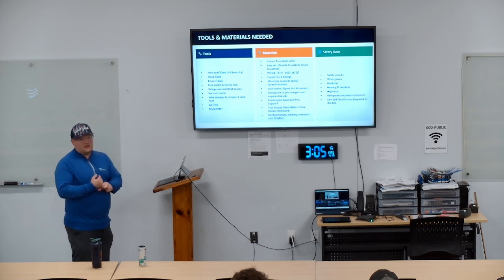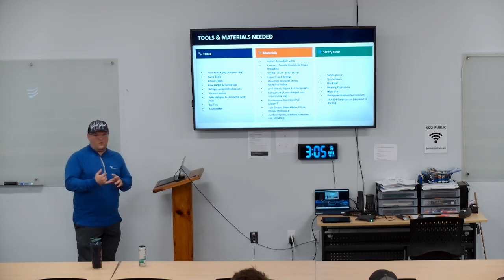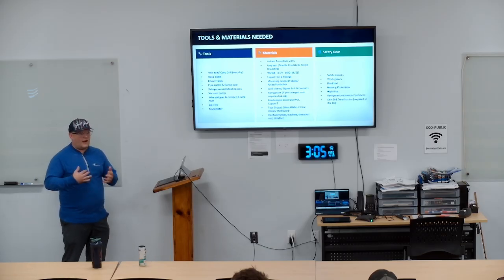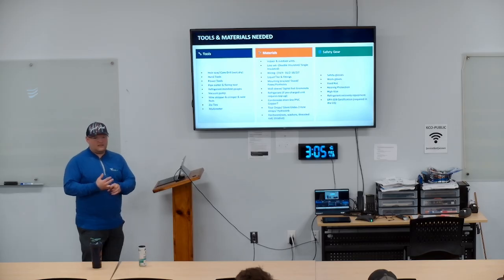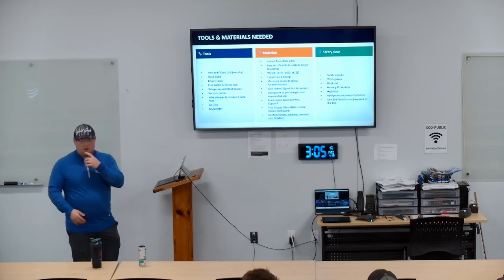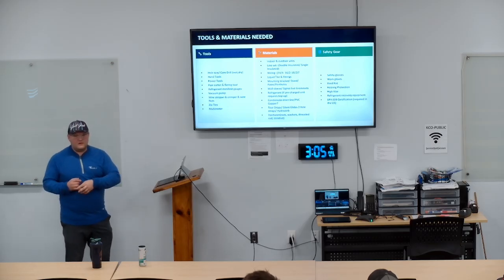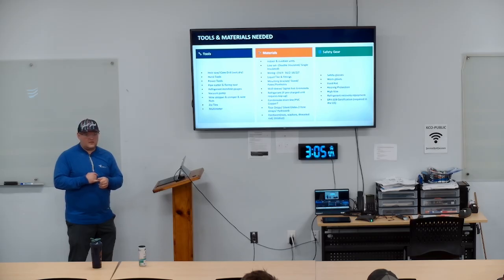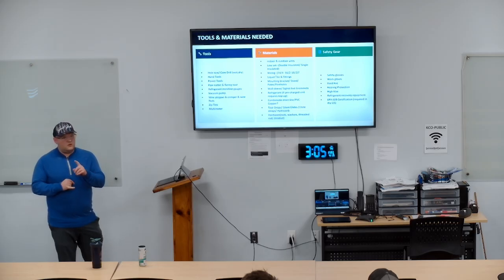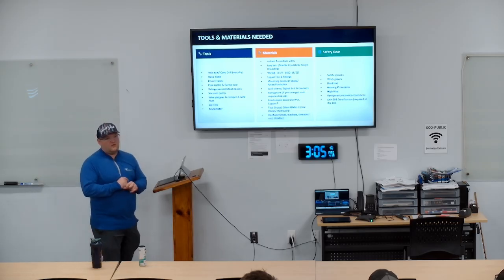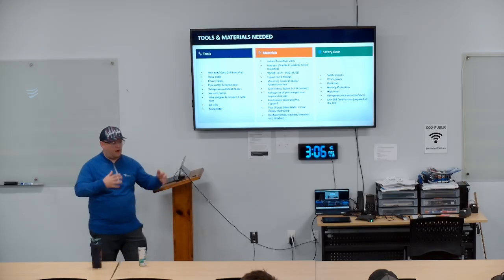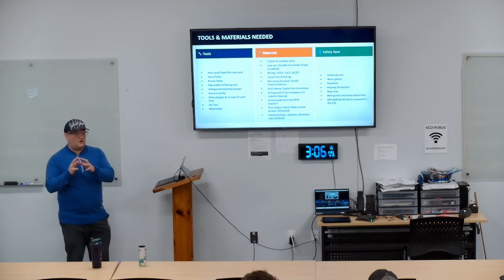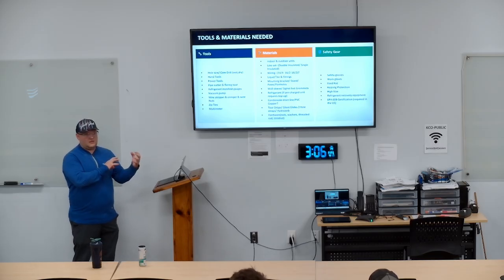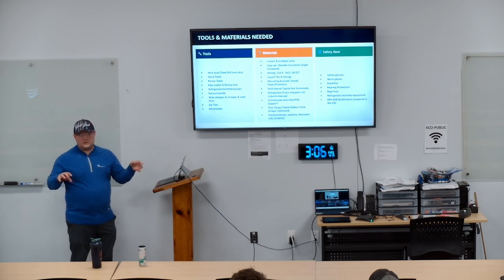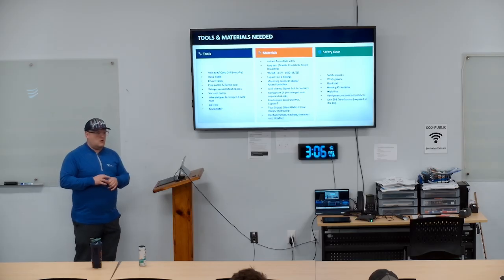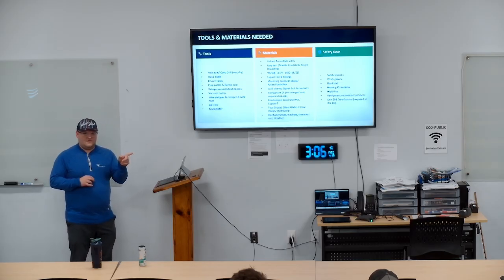So line sets, does anybody know when we use double insulated and when we use single insulated? I'm sure everybody's seen, sometimes it's double, sometimes single. So heat pump, okay, that would be what type, double or single? Double, okay. That is true, but not in all cases. The time that varies is if you have a vertical upright air handler with a TXV, a metering device inside of the cabinet, you do not have to insulate that liquid line, because it doesn't change state until it gets to the TXV.